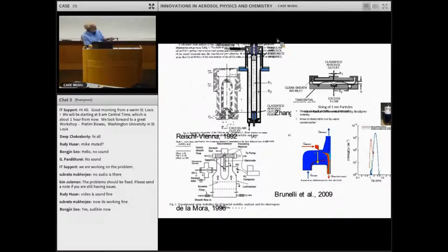We've built radial flow designs that have allowed us to make instruments that are better suited for small particles. There were some other people who built radial designs trying to measure big particles, but that's not so practical. We've ultimately taken this down to a very small instrument, one that you see is small enough to sit in a coffee cup, that actually will take us down to 1 nanometer. And with the current versions, with a resolving power of about 15 down to 1 nanometer in size. We can go very small.